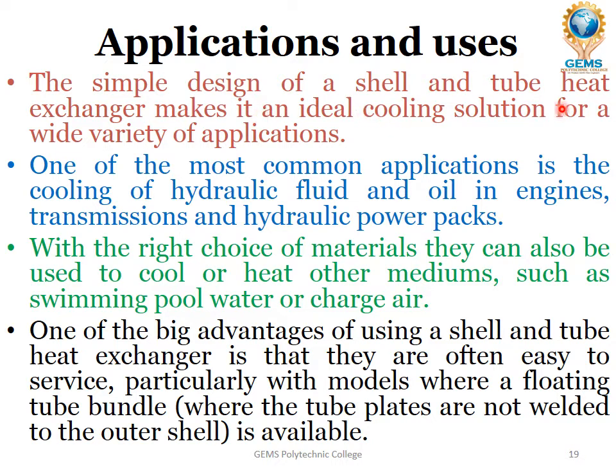The simple design of a shell and tube heat exchanger makes it an ideal cooling solution for a wide variety of applications. One of the most common applications is the cooling of hydraulic fluid and oil in engines, transmissions, and hydraulic power packs. With the right choice of materials, they can also be used to cool or heat other mediums such as swimming pool water or charge air. One of the big advantages of using a shell and tube heat exchanger is that they are often easy to service, particularly with models where a floating tube bundle, where the tube plates are not welded to the outer shell, is available.